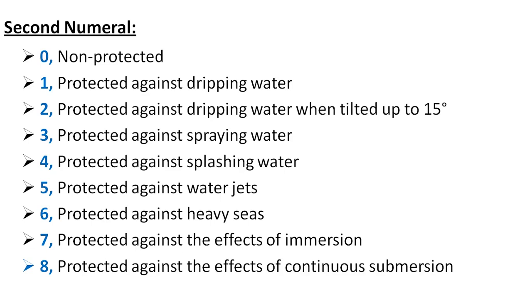The second numeral indicates protection against water penetration. When it is zero, it is non-protected — a device with IP_0 as the second digit has no protection against water and cannot be used for outdoor applications. One indicates protection against dripping water in the vertical direction.